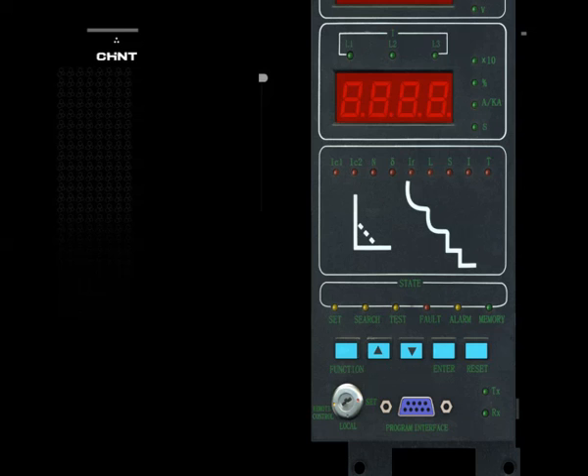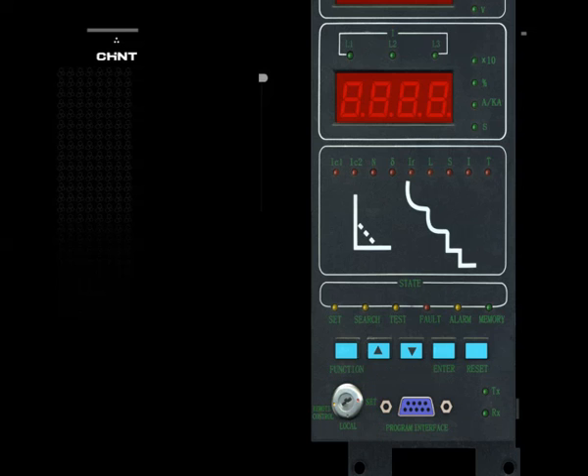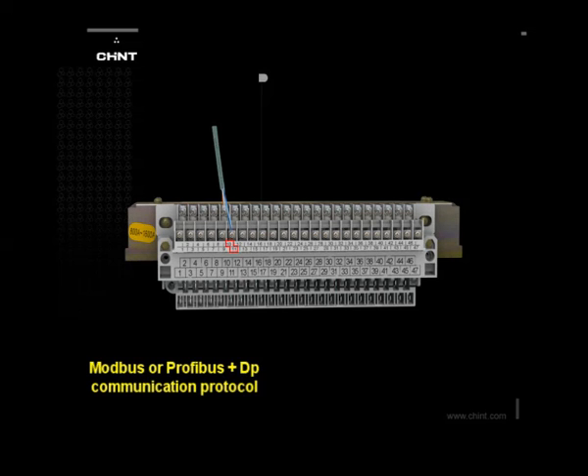Fault Inquiry of H Controller: The key lock is at set position; the function key is pushed until the inquiry light is lightened. The confirm key is pushed and the inquiry light is constantly lightened. The key is pushed to make the fault light flash, then the confirm key is pushed. The fault operating time and operating current are displayed, and the return key is pushed until the inquiry light is off. Communication Function: The key lock is at the communication position. Secondary wiring terminals 10 and 11 are connected by cables to enable communication functions.